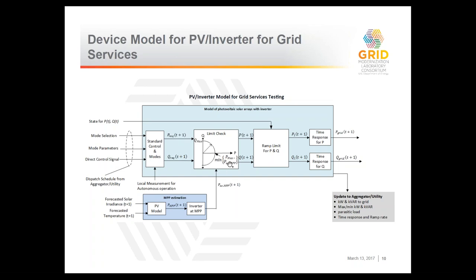And then obviously we have to make sure that we are not violating any limit. First of all, your P, the active power, cannot be more than whatever available power. Your reactive power will depend on your device rating, and your kVA also depends on your device nameplate rating. So all those limitations we have to satisfy, and if not, then some limits have to be placed on those P and Q, and based on those, we then go into a ramp rate, a ramp limit, which is basically telling if you're changing a step between, say, P1 to P2, can we jump there instantaneously, or will there be multiple small steps to go from P1 to P2?